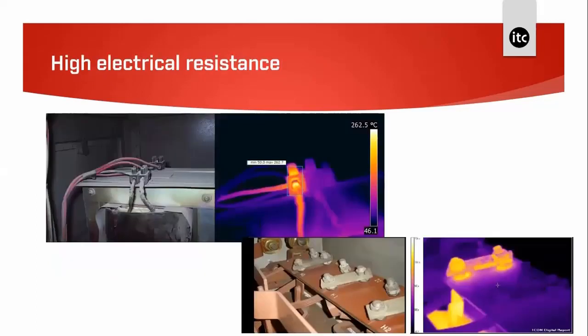These are examples of high electrical resistance on transformer connections. Both images use the iron color palette where white is hot and black is cold. If you look closely, you can see very definite elevated temperatures within both thermal images.